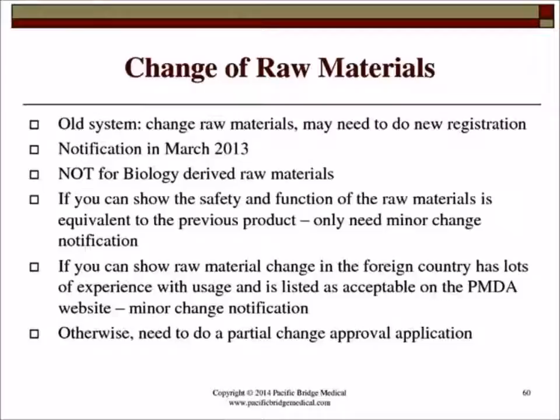So the key issue with a raw material change is that it does not affect the performance or the function of the device. Otherwise, if the raw material change does affect the performance and function, your MAH in Japan must submit an approval application for the product change, and the PMDA will review this raw material change, and the MHLW will decide on the approval of the partial change application. But instead of a partial change application, which is more complex through the PMDA and MHLW, the new raw material changes will be through a minor change notification. And of course, if you're unsure whether the raw material change has to be done through a partial change application or a minor change notification, you can always consult the PMDA.